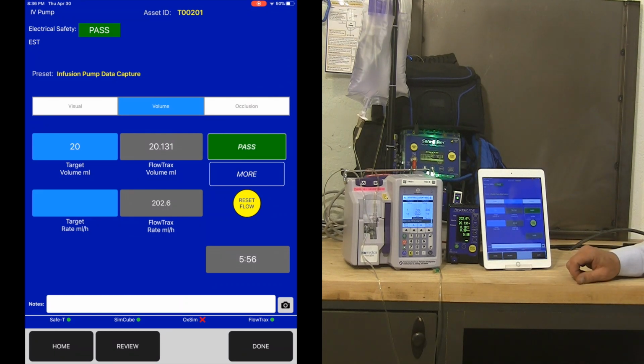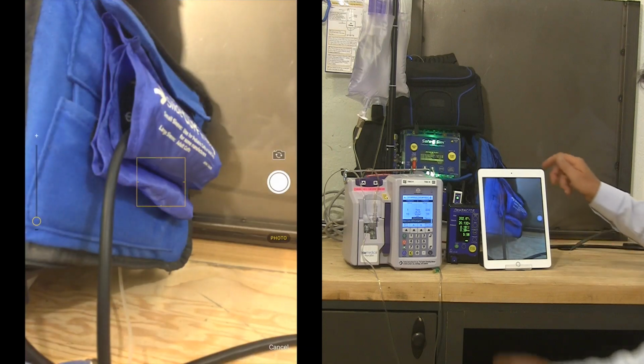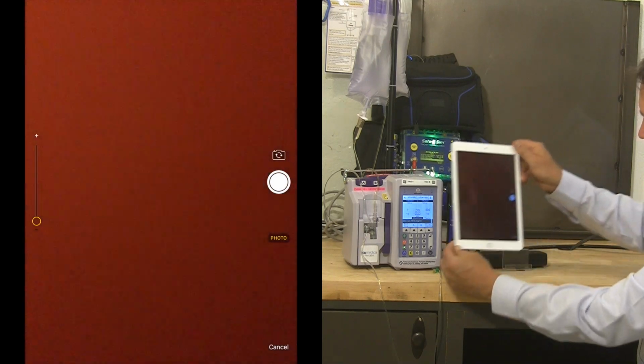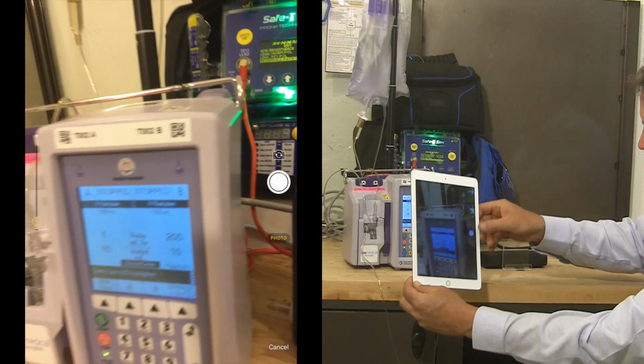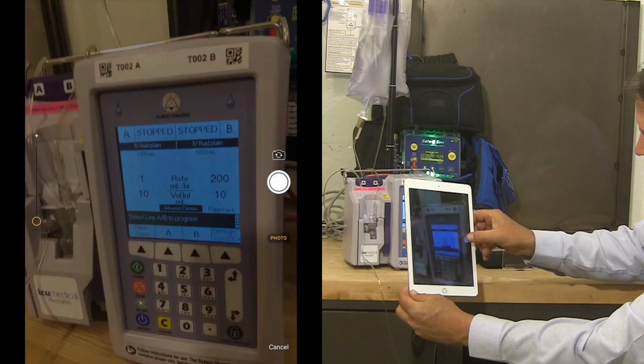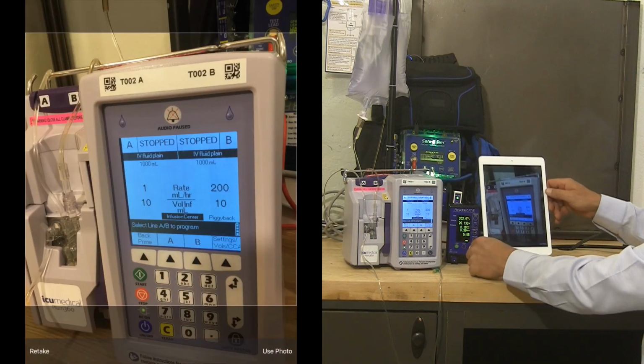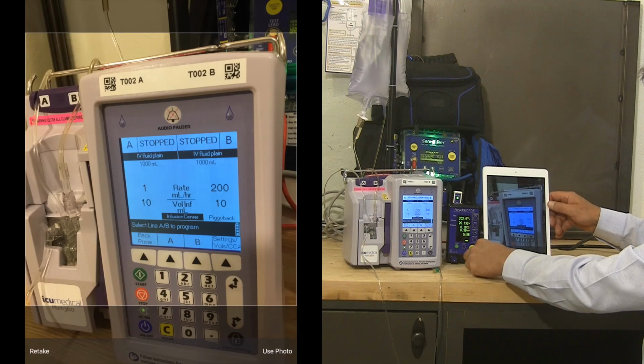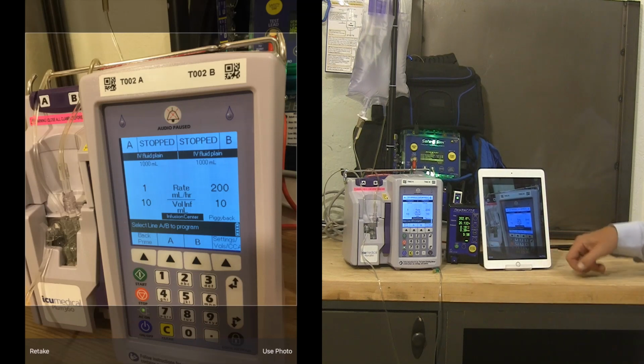If for any reason I need to run an additional volume test, I can simply hit the more button and run a second volume test or a third, and that will also be captured into the electronic record. I can take a picture of the IV pump at any point during the testing if I need that objective evidence of what I was doing on the IV pump, and that also becomes a part of the electronic record.